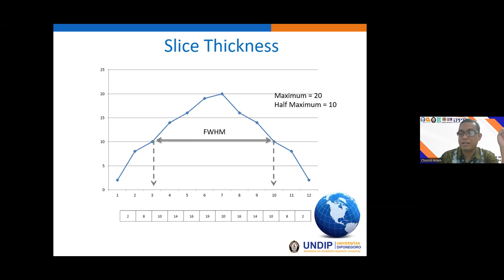It is very easy to measure using the IndoQCT. We can measure either manually or automatically, and we can measure based on the length of the line and also based on the full width at half maximum, by using the IndoQCT.